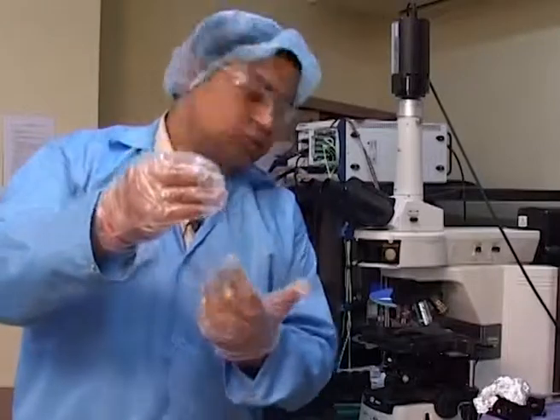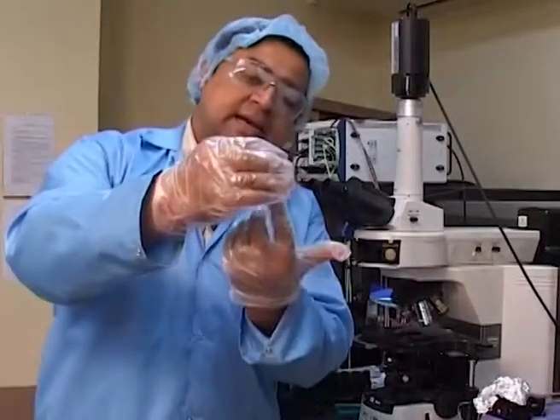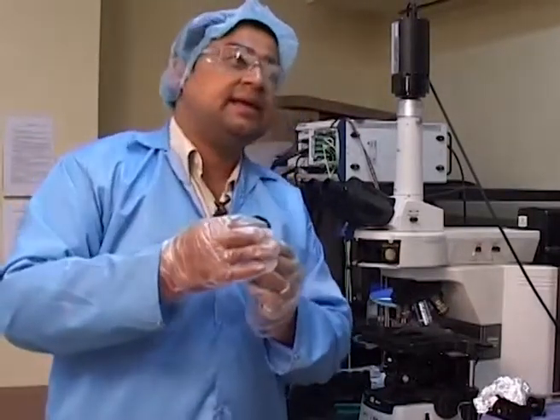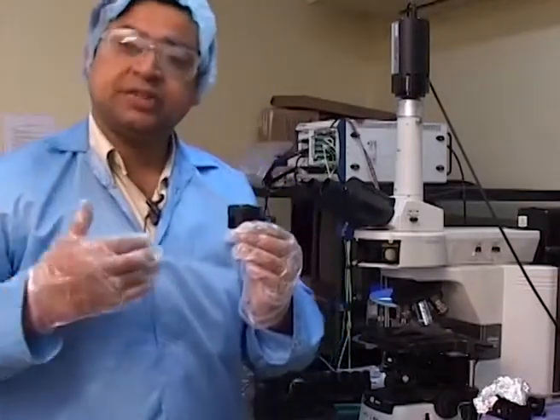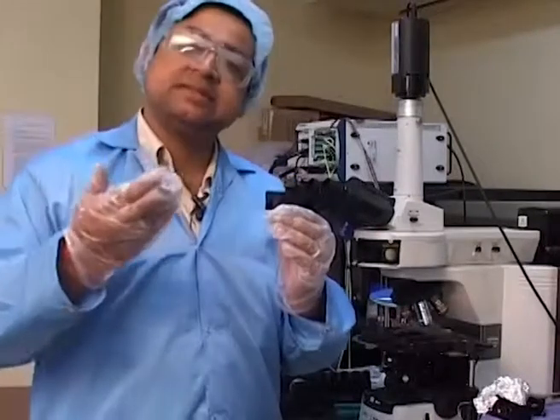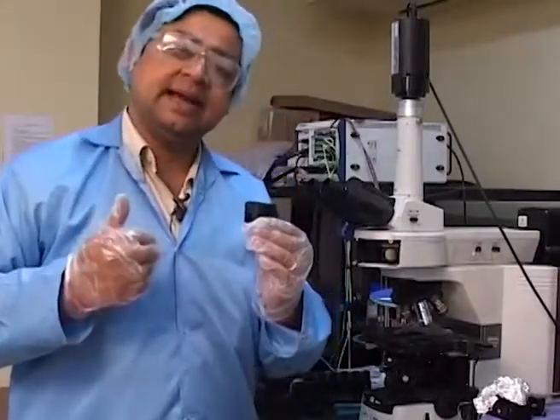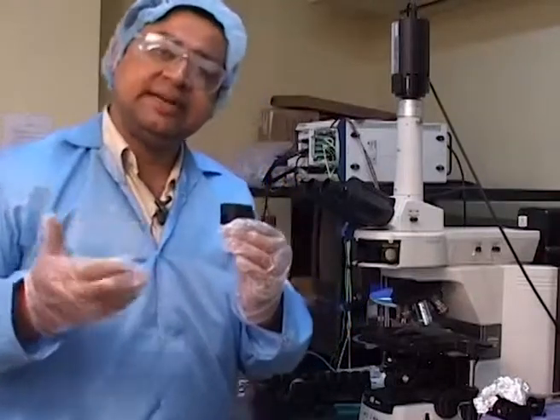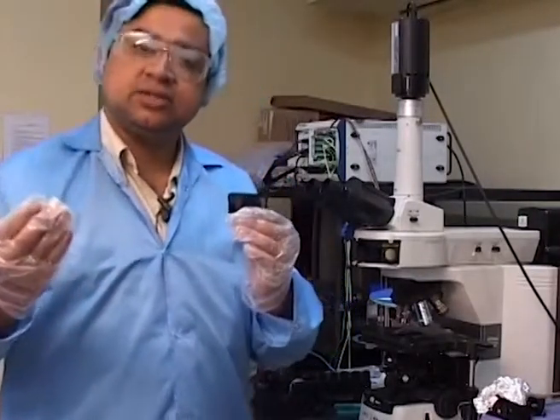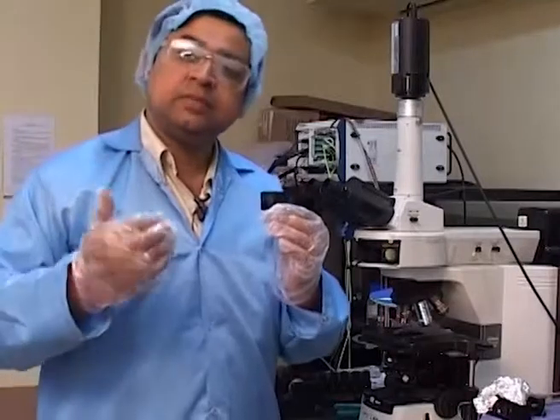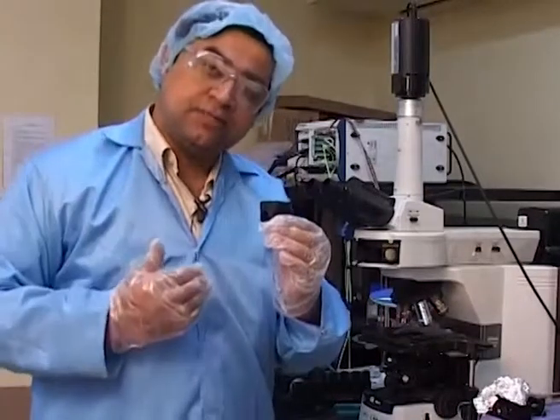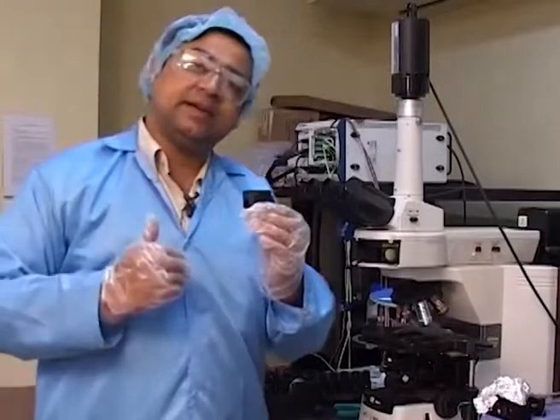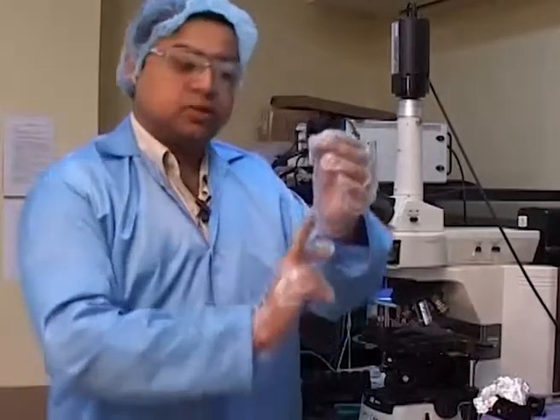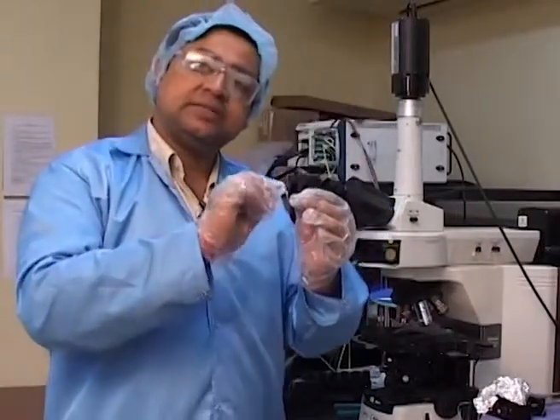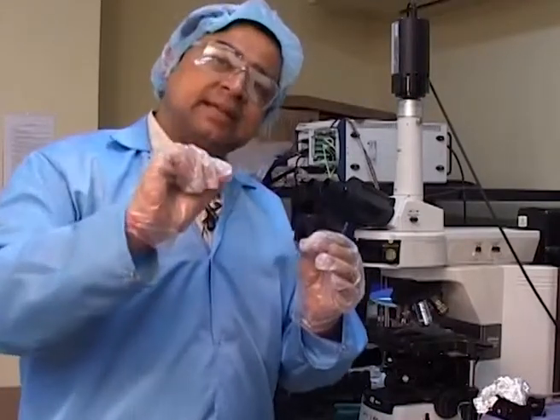Now, this light comes back through the objective and hits the mirror, and here, as you see, the dichroic does its job again. In this case, because of the Stokes shift, the wavelength generated by the fluorescence is on the higher side. Suppose we have a fluorophore which generates an emission in the range of 620 nanometers, which is above the 590 cutoff provided by the dichroic. So the light beam coming from the fluorophore through the objective is going to go past the mirror in the refraction mode.